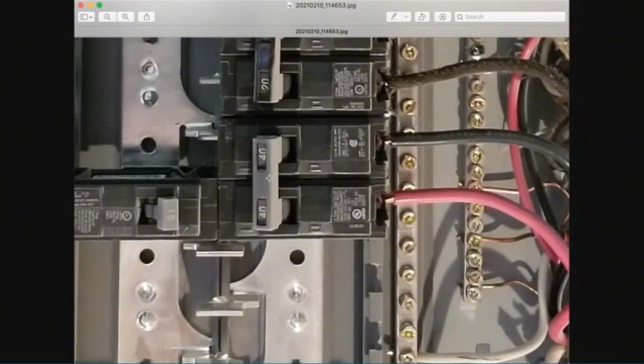When we look at our 40 amp circuit breaker, ladies and gents, the wattage for my stove is going to be 40 amps times 240 volts. That gives me a total of 9,600 watts. Then the safety capacity of that is going to be 80%.